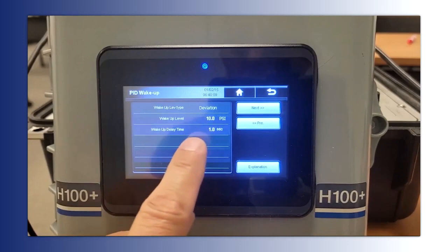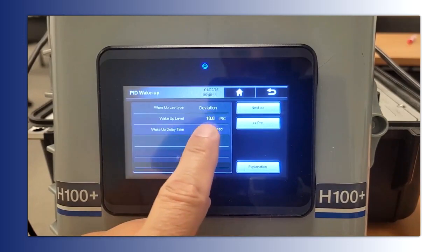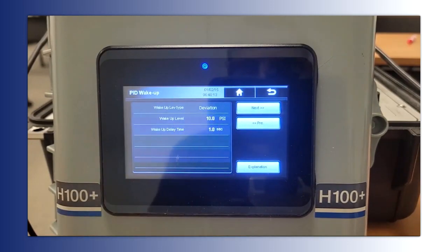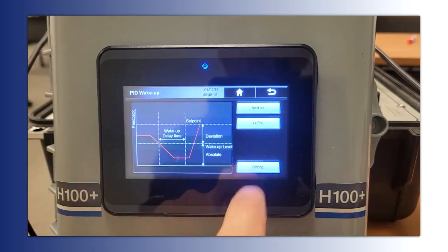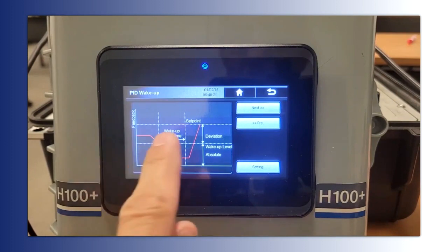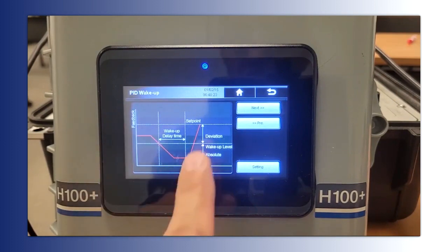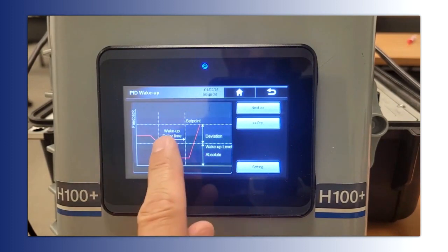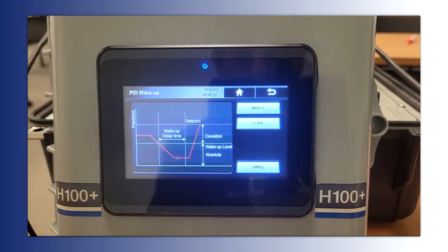Then we have our wake up level. So we have a deviation of 10 psi. So 70 minus 10 psi. That means we'll wake up at 60 psi. There's also some explanations here. So you can see, hey, if we have a pressure drop, it's a deviation from your set point, and then we hit this delay time, that's when the drive wakes up.